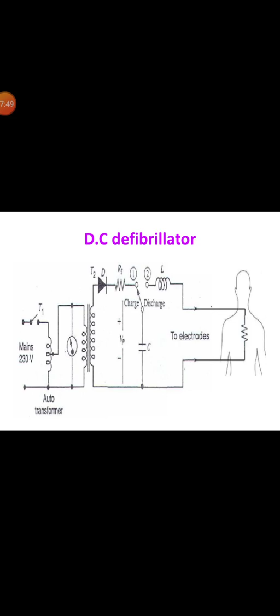An inductor in the defibrillator is used to shape the wave in order to eliminate a sharp, undesirable spike that would otherwise occur at the beginning of the discharge. Even with DC defibrillation, there is a danger of damage to the myocardium and the chest walls, because peak voltages as high as 6000 volts may be used. To reduce this risk, some defibrillators produce dual peak waveforms of longer duration at a much lower voltage. When this type of waveform is used, effective defibrillation can be achieved in adults with lower levels of delivered energy, between 50 and 200 watt-seconds.